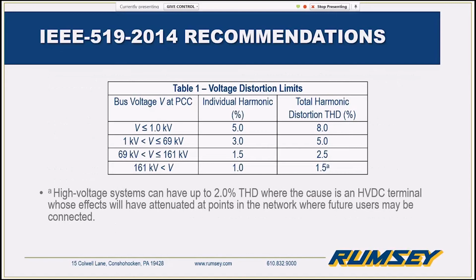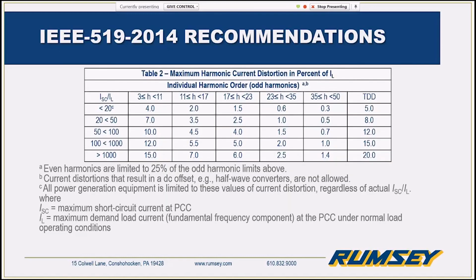A couple other changes that happened with 2014. So when we're looking at these charts and tables, we're going to go to the next one first actually, with the current harmonics. It used to be that depending on what percentage you fell into, trying to determine this was a little bit more complicated. What kind of process were you? Hospitals had to meet 3%, certain manufacturing met 7 or 9%. Now it's clearly defined to say you fall into a band depending on the maximum short circuit rating of your utility transformer and the total demand load current that you have.